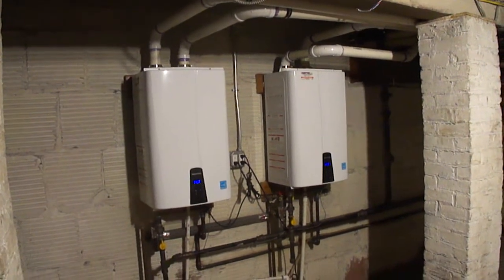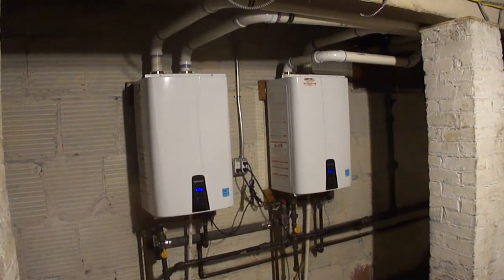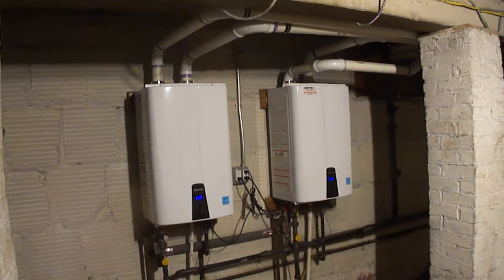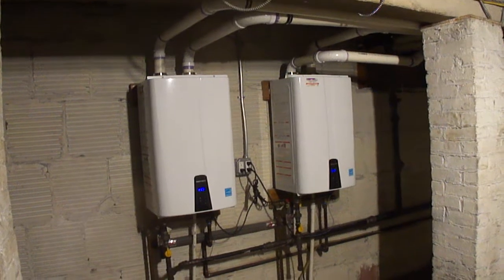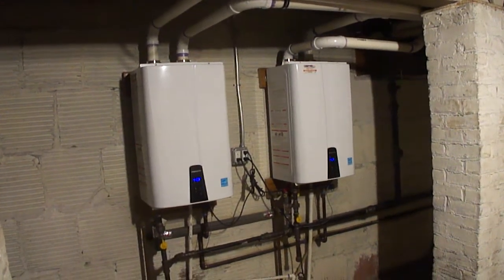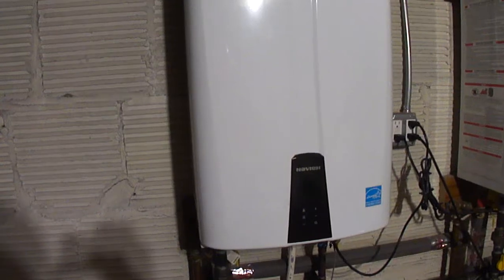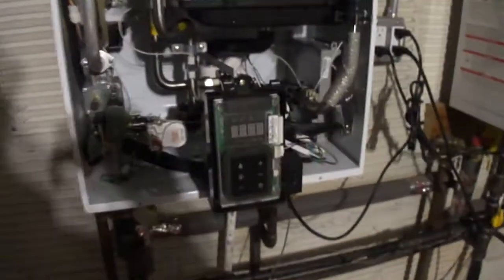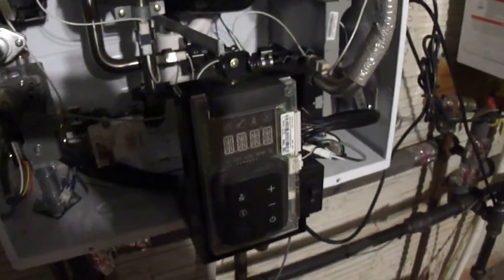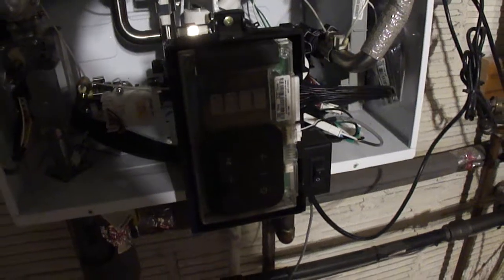I am with Handyman of America, and today I'm going to show you how we maintain this beautiful Navien hot water on demand hot water units. We begin working on the unit first by shutting it off and removing the cover. Once we have the unit cover off, we'll begin to set the machine up so that we can clean it. Several areas need to be cleaned.